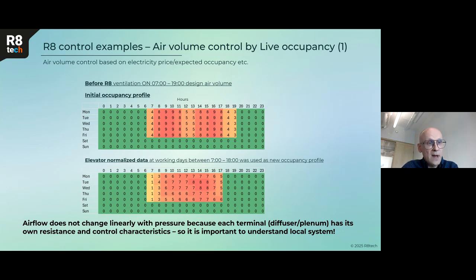But what we are doing is, firstly, we add an initial occupancy profile. It means 10 is where the occupancy is maximum, and 0 is unoccupied time. Based on that, we are controlling the ventilation fans, plus adding other input parameters like electricity price, etc. And if it is available, we are using additional data sources. For example, elevator data. New elevators have their own API, and where we get elevator data, we can adjust our original occupancy profile, so we can act more like the building is actually acting.